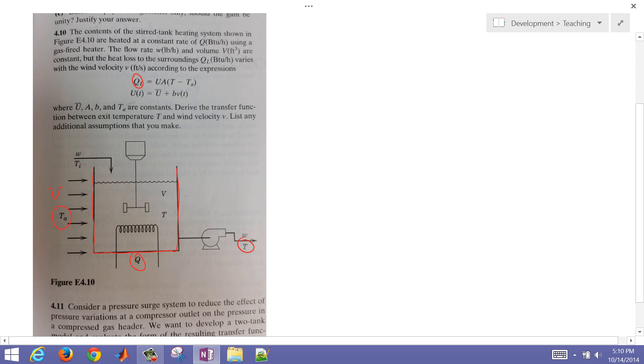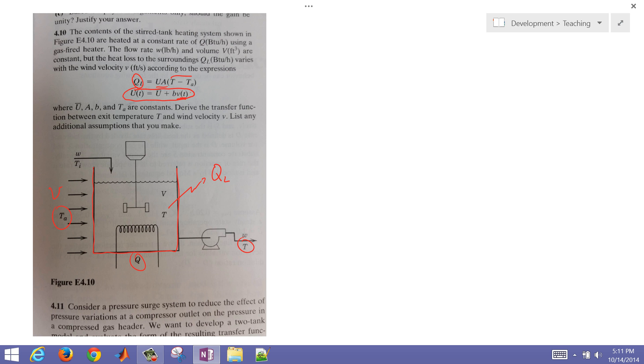So we have a Q_loss — that's the heat transferred away from the tank — and that's dependent on the overall heat transfer coefficient times the difference between the tank temperature and the ambient temperature. That heat transfer coefficient is going to increase as the wind velocity V(t) increases, and we're going to lose energy at a more rapid rate.